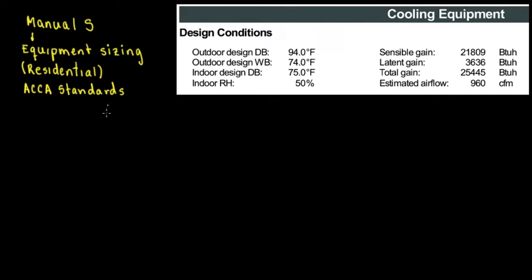It's a method. So, this is also a book. It's available online if you go to the website of ACCA and you're going to be able to find anything residential. You're going to have Manual J, which is heat load calculations, Manual S, which is Equipment Sizing, and Manual D, which is duct design. So, generally, it comes in this order.